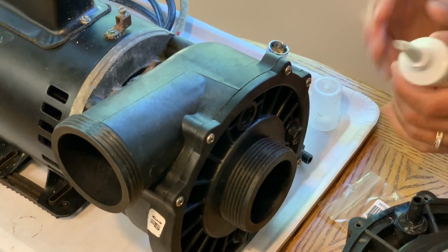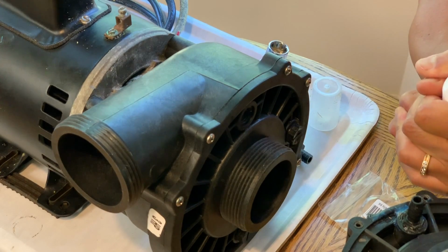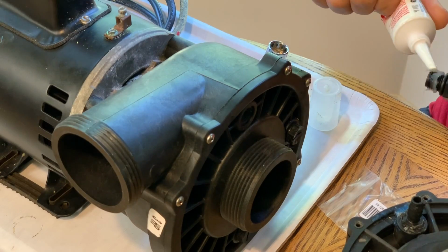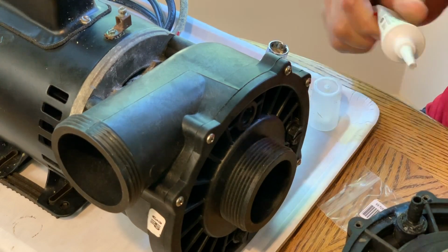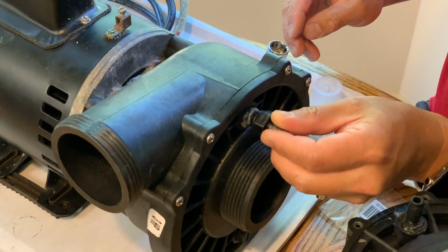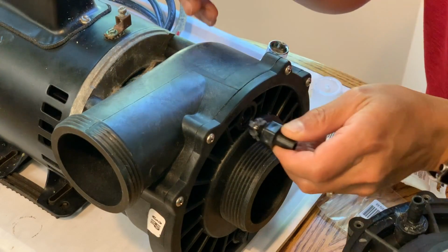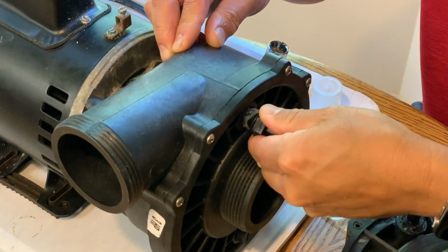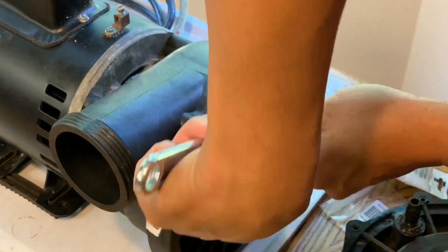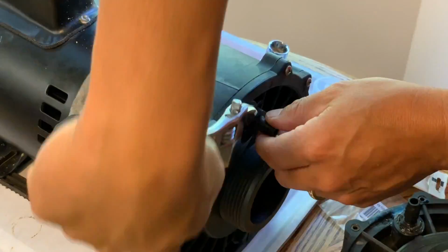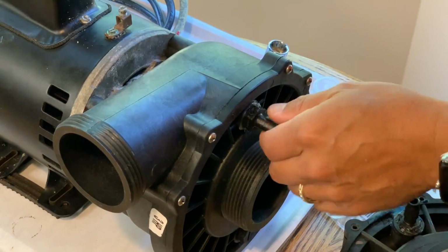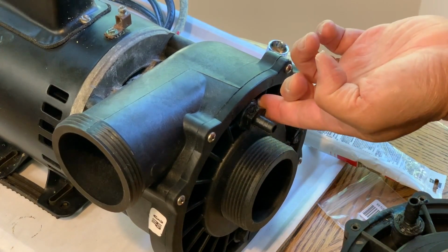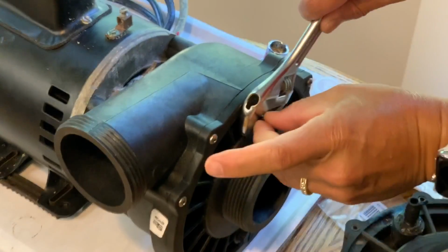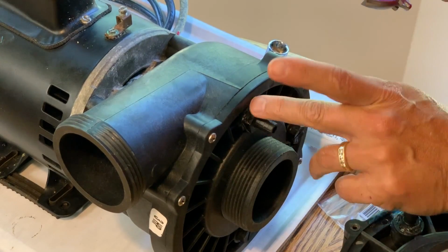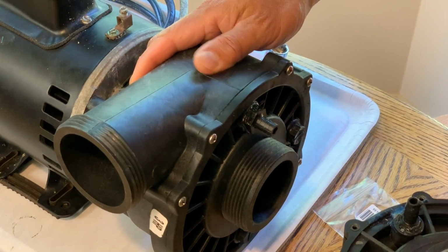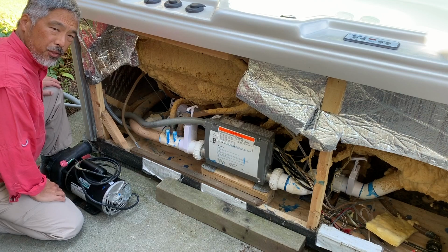And we're going to use some silicone to seal these threads. And this is actual silicone sealant, so this will set up semi-permanently. Here's the O-ring on there. Just want to make sure I don't cross thread this thing. All right, looks like that O-ring should be seated down in there. This looks like it's actually sitting pretty flush. This should now be ready to reinstall. Now we have to reverse the removal process to put the rebuilt pump back in.